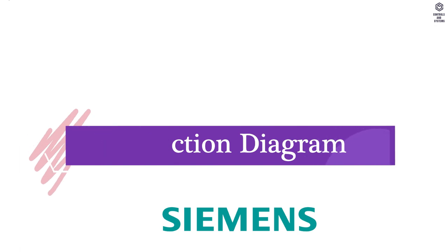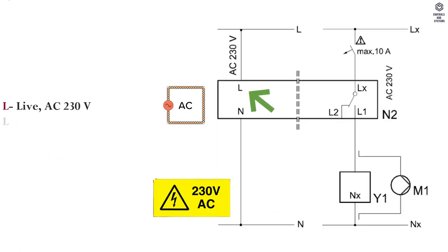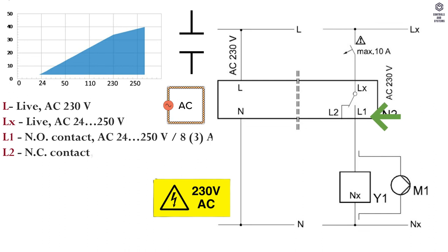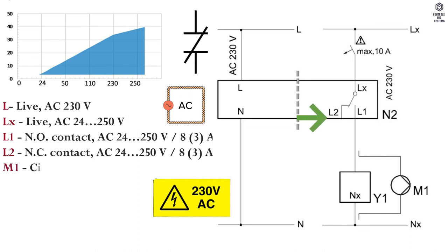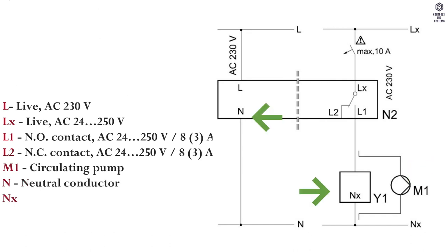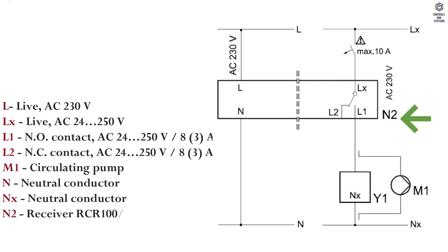Connection diagram: Terminal L is live AC 230V. Terminal LX is live AC 24 to 250V. Terminal L1 is NO contact. Terminal L2 is NC contact. Terminal M1 is circulating pump. Terminals N and NX are neutral conductor. Terminal N2 is receiver RCR100/433. Terminal Y1 is actuating device.